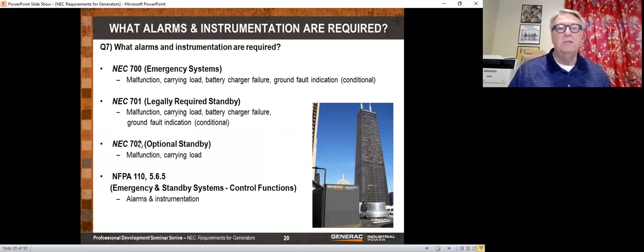If we go down to 701, now this is your legally required, and notice that it used to not require ground fault indication. Now it's conditional, and in most cases it actually doesn't. NEC 702, this is your optional standby. All that has to do is malfunction and carrying load. Now that I've told you that, I'm basically going to tell you that I lied. And that is for this reason.